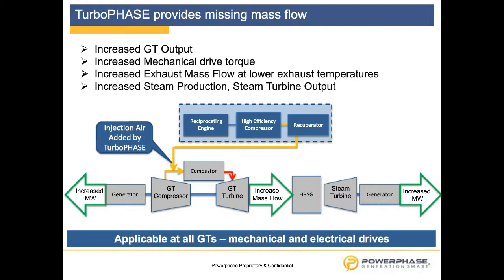And then on the upper portion of this picture, you see the blue framed box, which is reflecting our Turbophase module. You see a reciprocating engine, which is either liquid fuel or gas fired, that drives an intercooled multi-stage compressor. I come to that point later on. With the exhaust gases, we are heating the recuperator, the rooftop component. And once the air is matching the exact parameters of the given gas turbine compressor discharge in terms of temperature and pressure, then we are going to inject the air into the wrapper prior to the combustor.